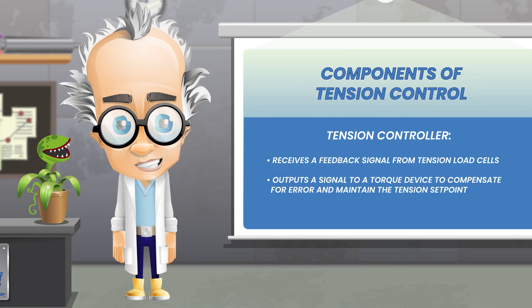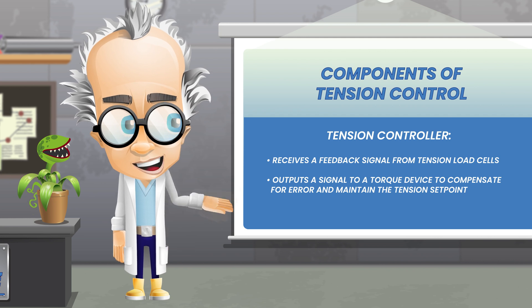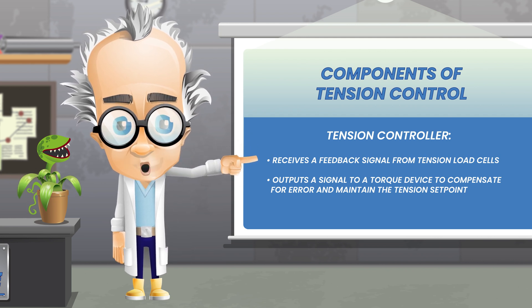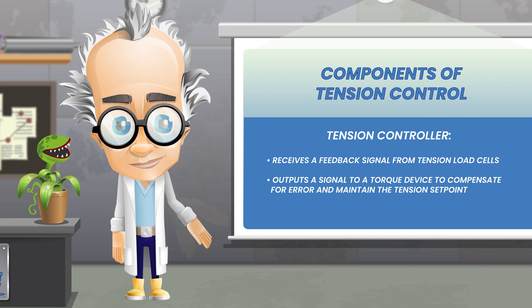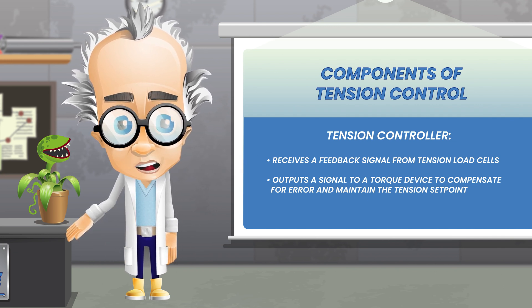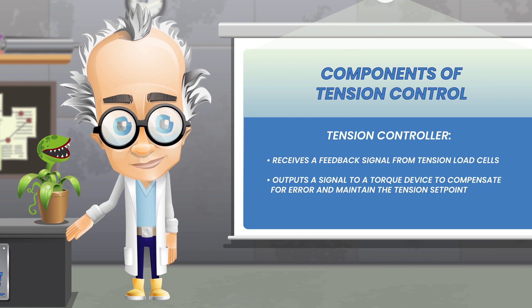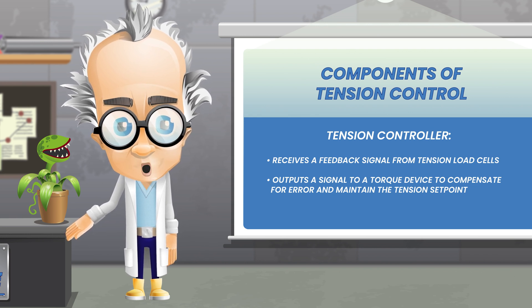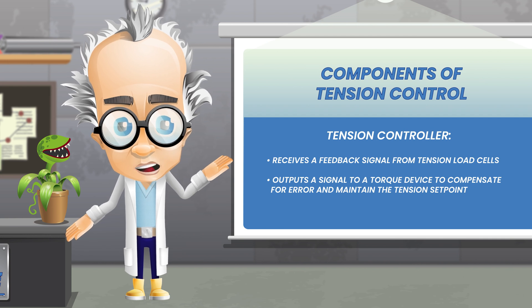During operation, a tension controller uses the feedback signal from the load cells to adjust the torque device and maintain a desired tension setpoint. If the tension reference signal from the load cell is too low, the controller will automatically increase torque output to compensate and increase tension. If the tension is too high, the controller reduces torque to achieve the desired setpoint.